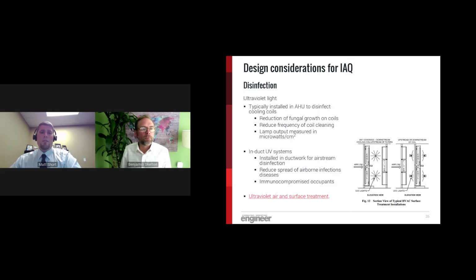For equipment disinfection needs, ultraviolet light is commonly used in HVAC equipment. The most common application of UV is to install the UV lamps in conjunction with the cooling coils and air handling equipment to prevent fungal growth. An example of this type of installation is in the image to the right, where the lamps are shown installed downstream of the cooling coils.